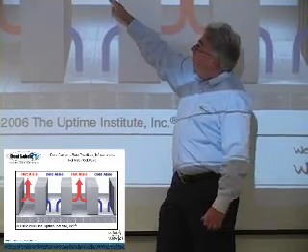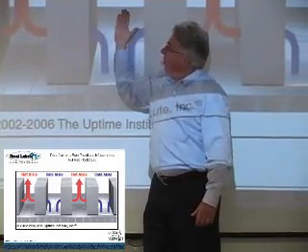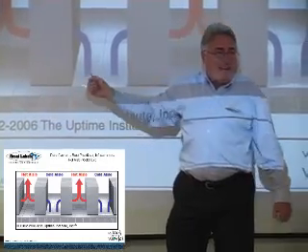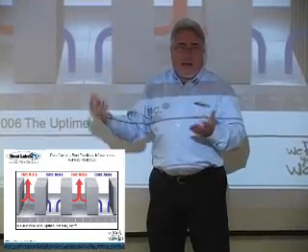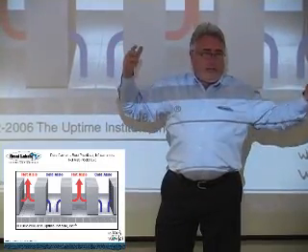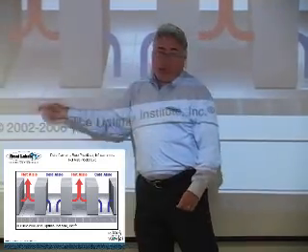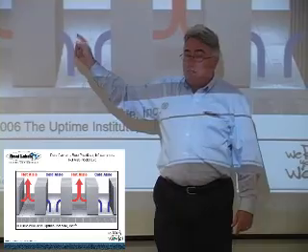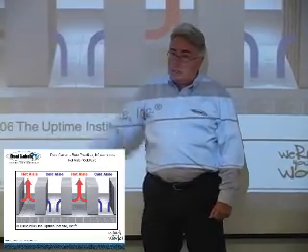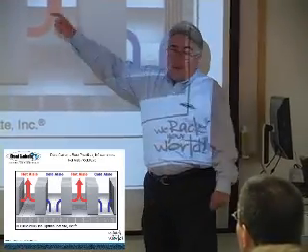We've seen other people put fancy metal walls on top and then put doors on the sides of rows and everything. Okay, they got a couple, but this is what we're talking about. You spend all the money for the CRAC unit, and now you have to buy more stuff to create and block off air. It seems kind of crazy. So that's the first thing that I would recommend that you do: if you do have those, pop those tiles out, stick them in the cold area, and then draw the solid in. Any questions on what we've got going on here?